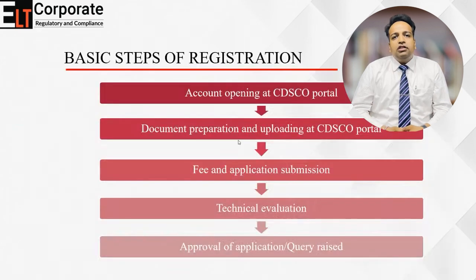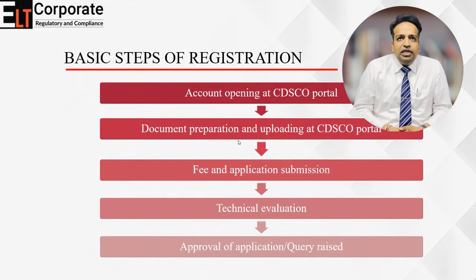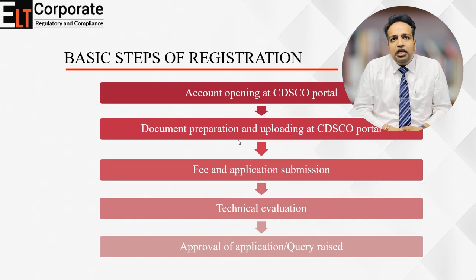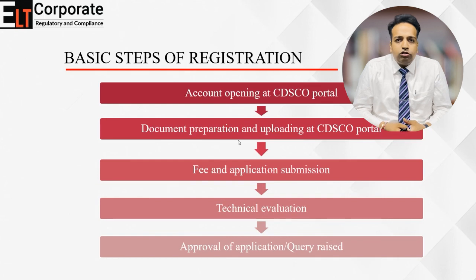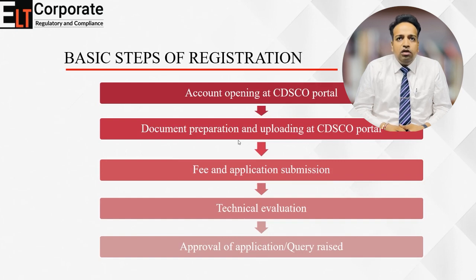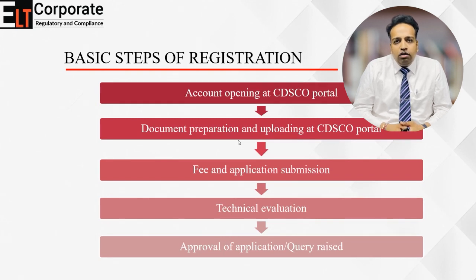Let's have a glance at the basic steps of registration. The basic steps begin with opening an account on the CDSCO portal, then preparing documents and uploading them to the CDSCO portal, then submitting the fee. After fee submission, government officers will technically evaluate the documents and may raise queries. Once you respond to those queries with appropriate replies, approval of the application will follow. In most cases queries do persist, since in India the medical device regulatory environment is relatively new.